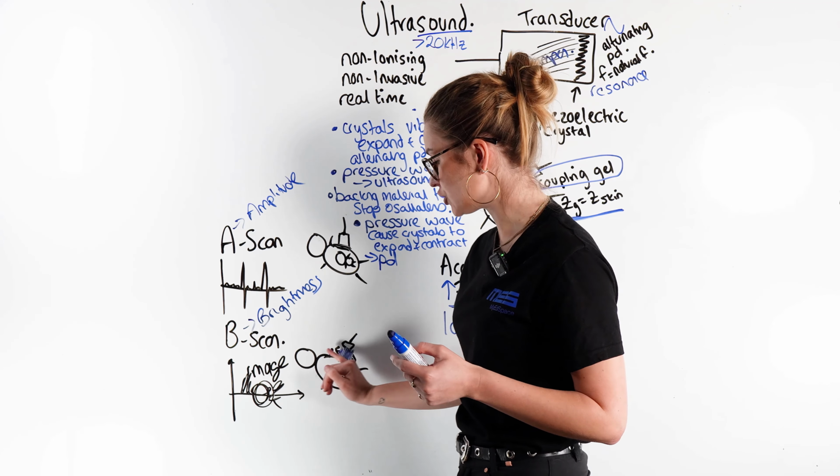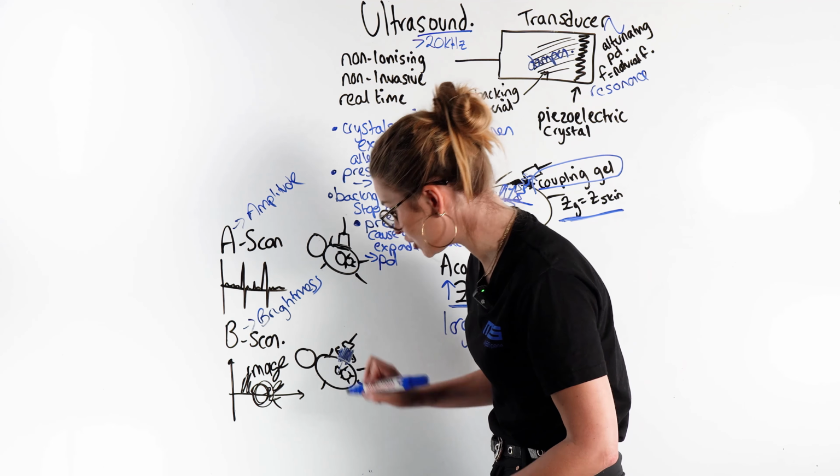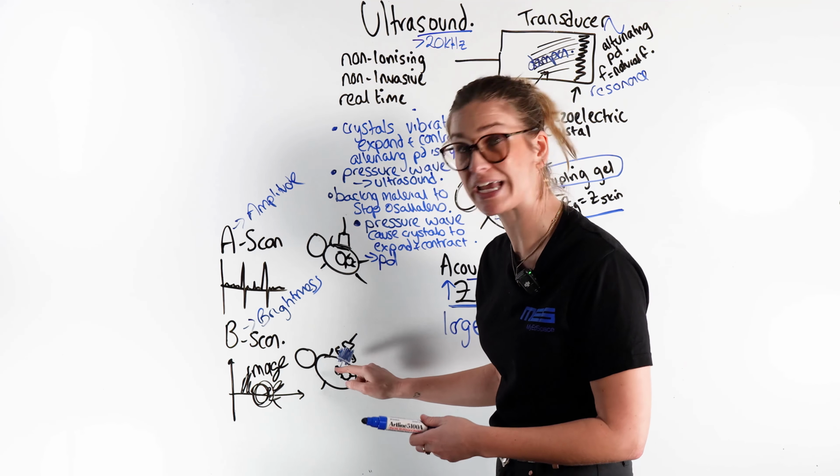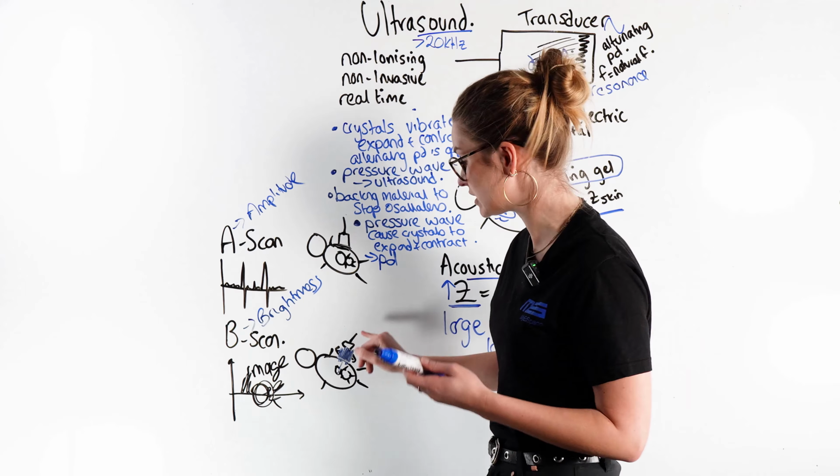And we know the location of the transducer because there are different resistances that it uses. All you need to know is that it uses the linear location and how much tilt they applied. When you're doing an image, the transducer and the target have to be perpendicular to each other, and if they're not perpendicular, you can't get that image. So that's why you have to rotate it around, because not everything inside your body is going to be perfectly perpendicular to that line of sight.